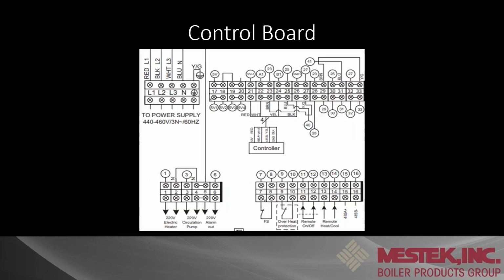But the main focus, I wanted to give you a zoomed-in look here where the power supply is. One thing to keep in mind is it is three-phase, so you're going to have your three legs of power, L1, L2, L3. We want you to run a neutral as well and a ground. The reason for the neutral is if there are any components that are going to run off 120, like for instance, we'll send 120 to a step-down transformer, we need to have that neutral there. Also, if you're wiring a pump back to this unit, we've got to have that neutral if it's going to run off 120 volts.